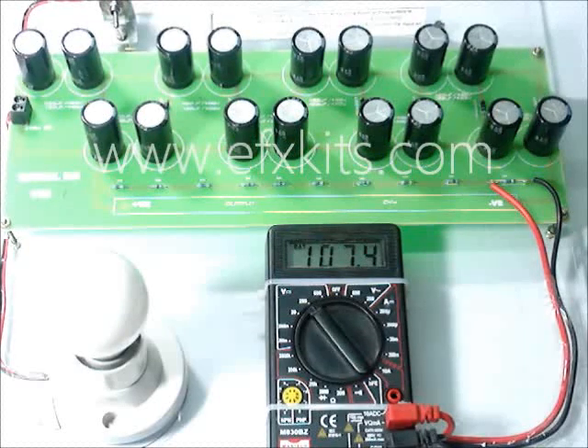It's a dangerous voltage, and we would not want to measure this 2 kilovolts directly with any meter. That's why we made a potential divider arrangement and took a connection from one limb of it. You can see the voltage is stable now at 108.1; multiplying by 20 gives more than 2 kV. That is the voltage available from a simple 230 volt AC supply.